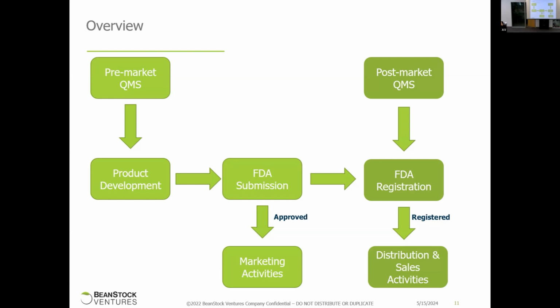So once you get pre-market approval, you can start marketing your product, but there's aspects of the FDA, which includes registration, to be able to sell and distribute your product. So there's two pieces. The registration is looking at your quality management system primarily. Your FDA submission, or your approval or clearance, is looking at the technical specifications and the testing of your device.